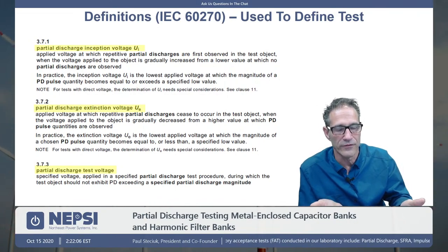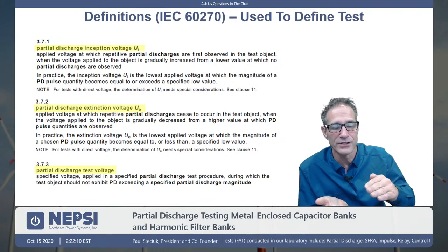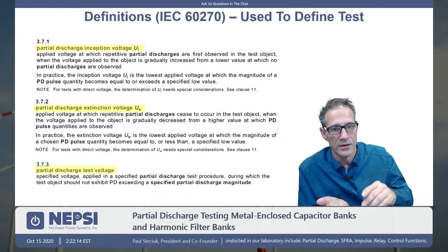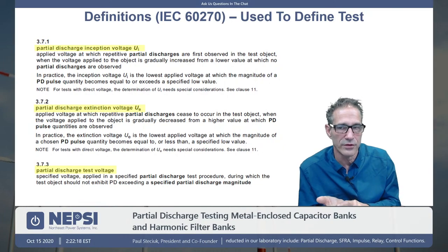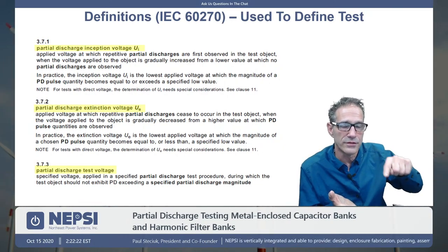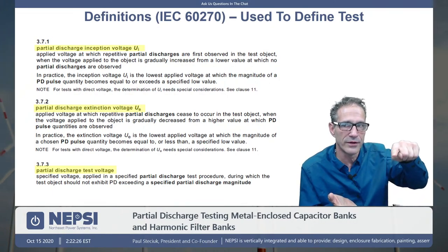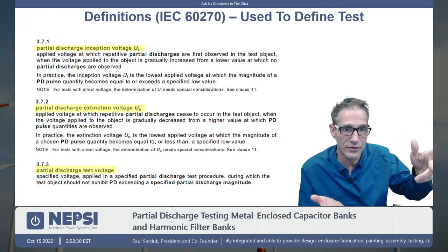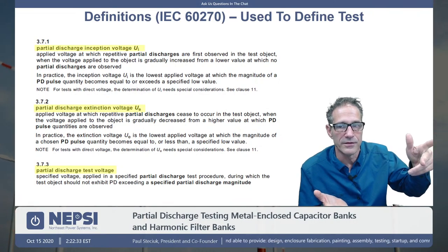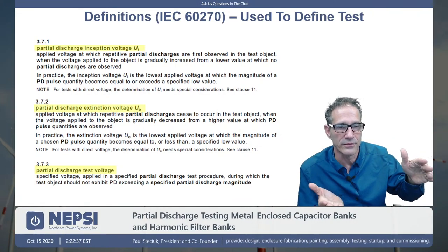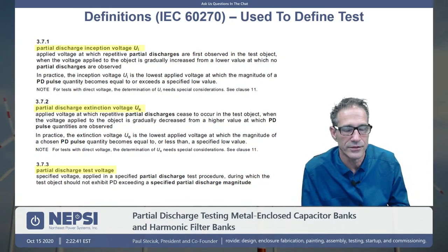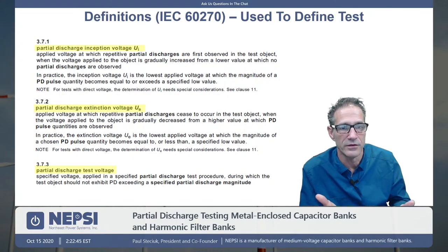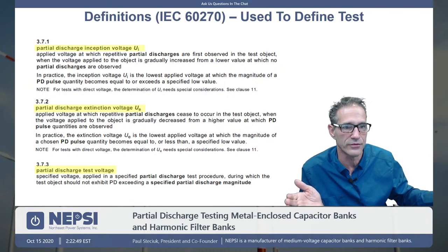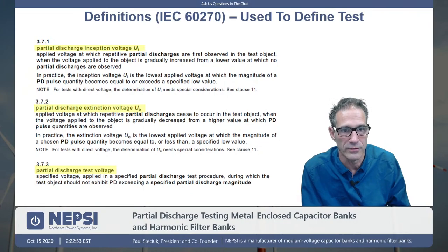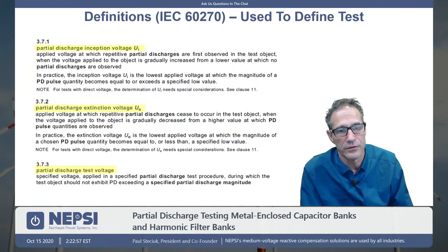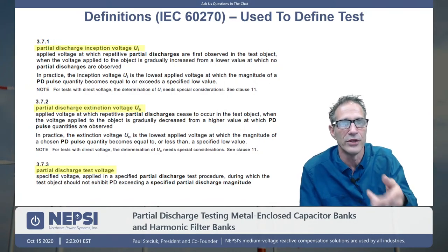So say I have a 34.5 kV system, I would certainly want to make sure that my extinction voltage is at 38 kV or above, because this is really one of the reasons you do this test. If I have an overvoltage in the system, that overvoltage could theoretically bring me up into the inception voltage region, and I could start to have partial discharge in my equipment. And then say this overvoltage condition goes away 3 seconds later. Say we had a load rejection issue. We dropped a bunch of load. You might get a 15 or 18% overvoltage because you have 40 megavar capacitors on, and we just dropped a whole grinding mill. That overvoltage could bring you into a situation where you have partial discharge. You reached your inception voltage.